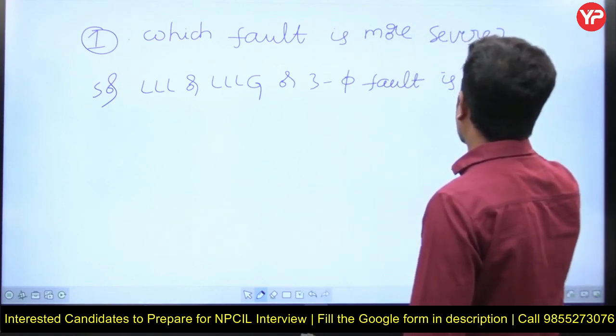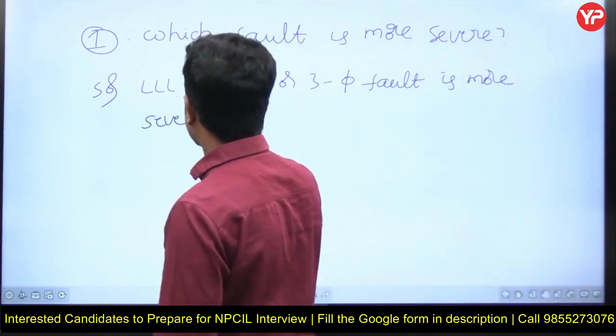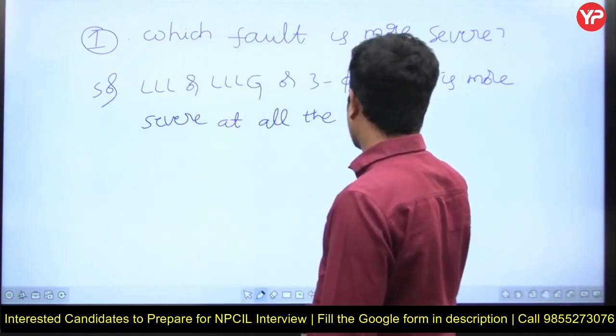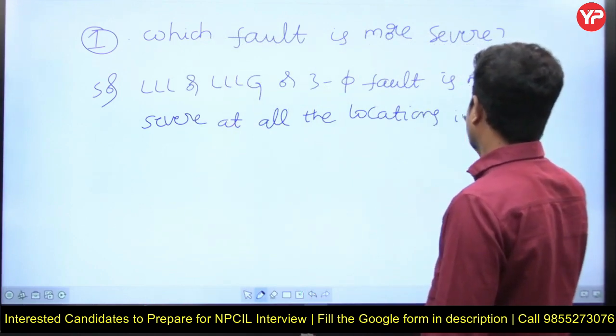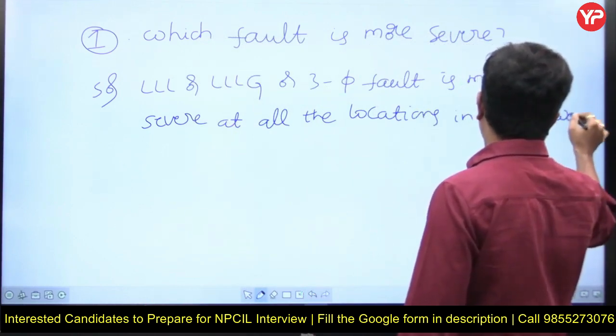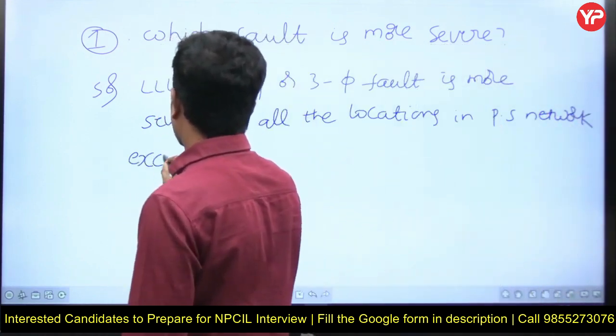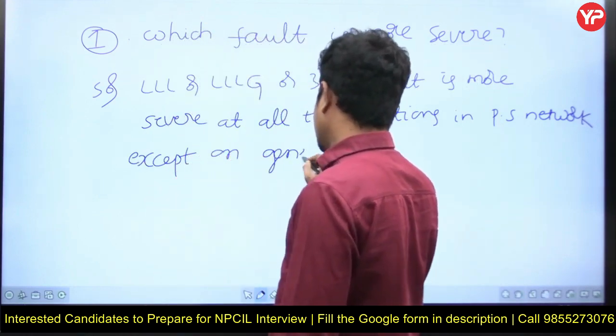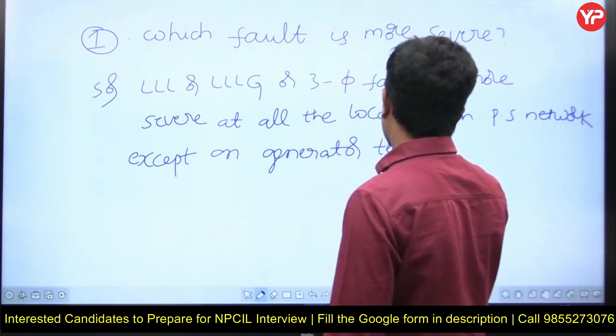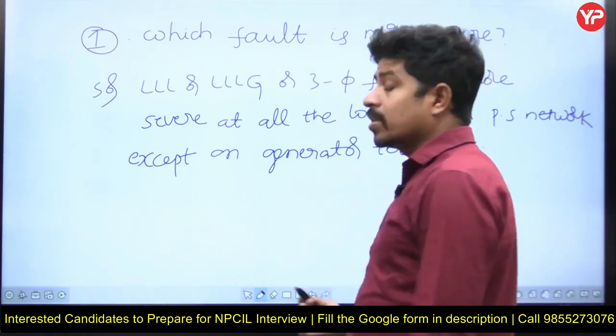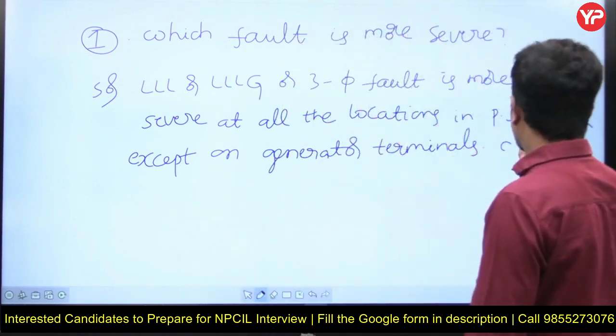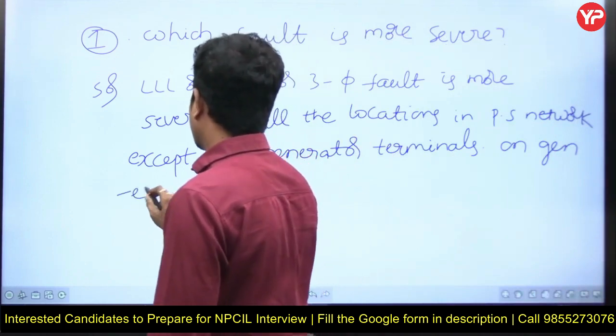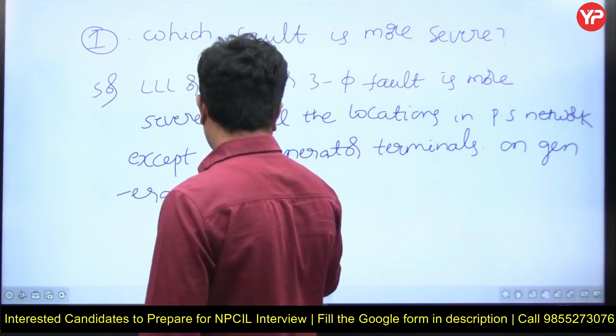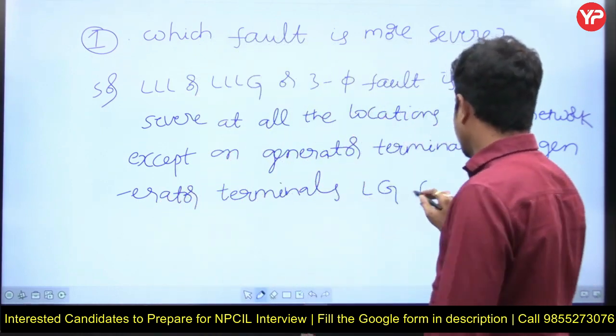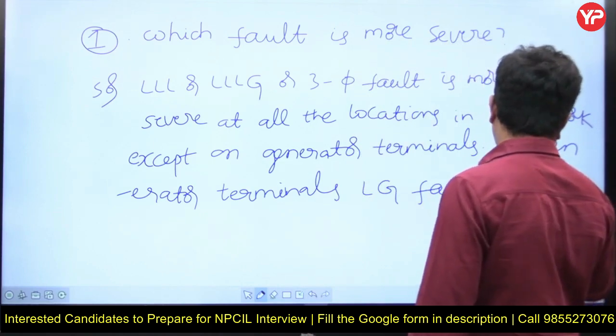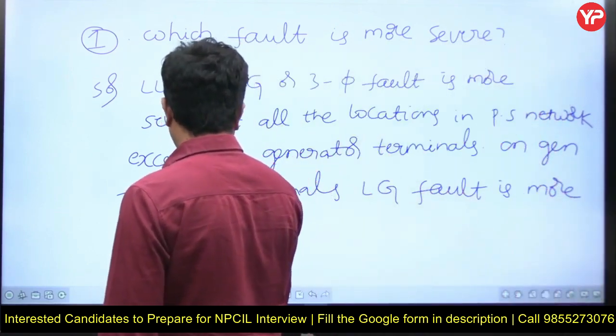Fault is more severe at all the locations in the power system network, except on generator terminals. On generator terminals, LG fault is more severe, right? Yes, LG fault is more severe.